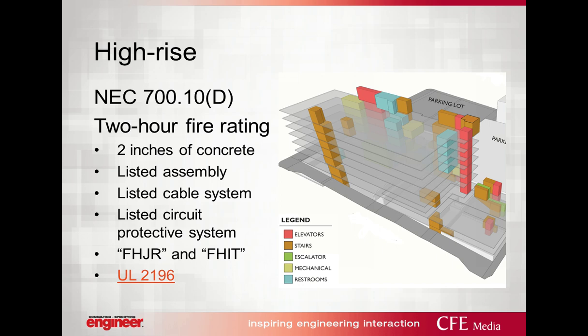But what they're talking about is, say, mineral insulated cable or special fire-resistant metal clad cable. Maybe it'd be RHW-2 in an RTRC or phenolic resin conduit. And you may even have power-limited fire alarm cable that would be located in EMT.